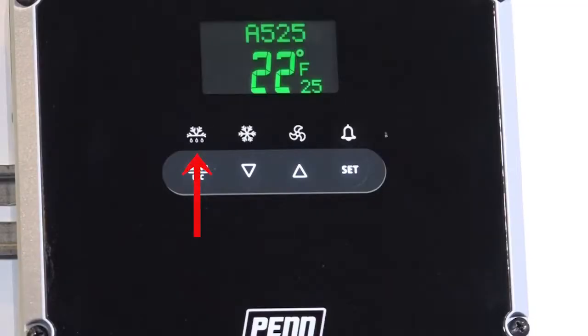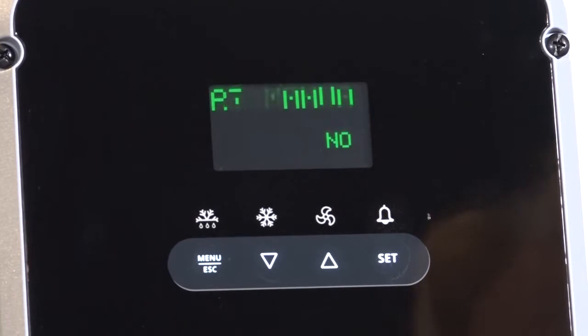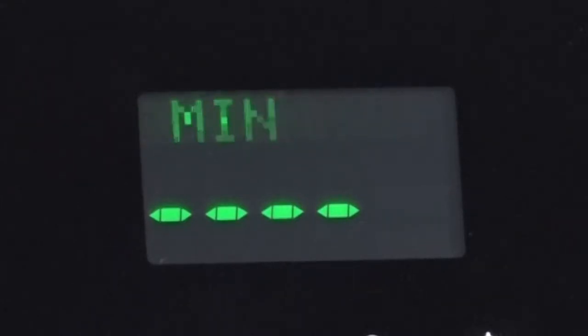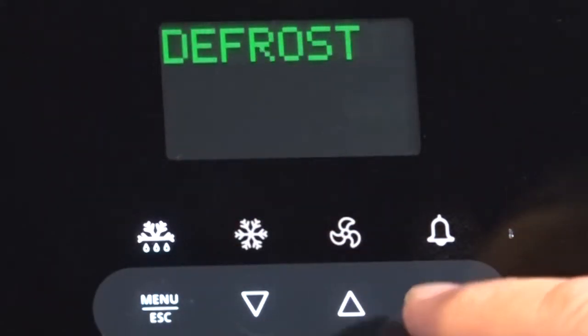There are 4 activity icons that indicate the status of the system. The first icon is the defrost icon. When illuminated, it signifies that a defrost cycle is taking place. You'll notice that the main display also indicates that a defrost cycle is occurring. The display has a timer that tells you how much time is remaining in the defrost cycle. To initiate an immediate defrost cycle, simply press and hold the defrost icon for 5 seconds. The main display will ask to confirm the choice to start the defrost cycle. To terminate a defrost cycle, press and hold the illuminated defrost icon for 5 seconds. Again, the main display will ask for confirmation to terminate the defrost cycle.